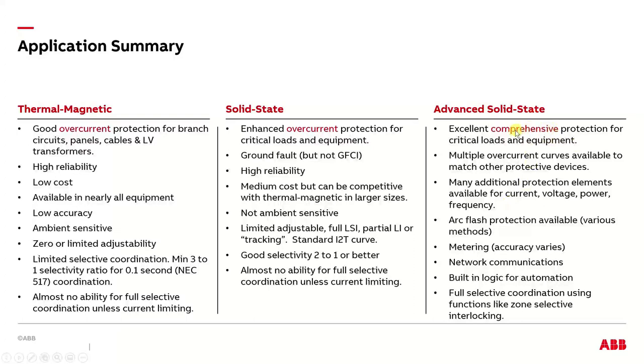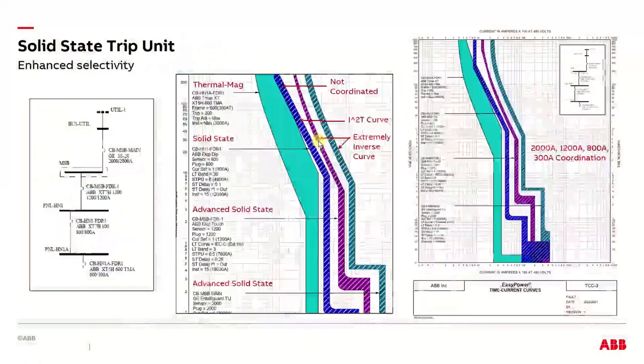And then when you get to your advanced, we kind of covered that: comprehensive protection, a whole host of different protective elements for current, voltage, power. I haven't really got into this, but there's some good arc flash protection that you can build into the systems, metering, communications, built-in logic. You can get these to be fully selective by using technologies like zone selective interlocking. We can do differential schemes. So there's a whole host of ways you can get these to be a fully selective system. Here's just a couple I'll try to get through real quick because I know we're running out of time.